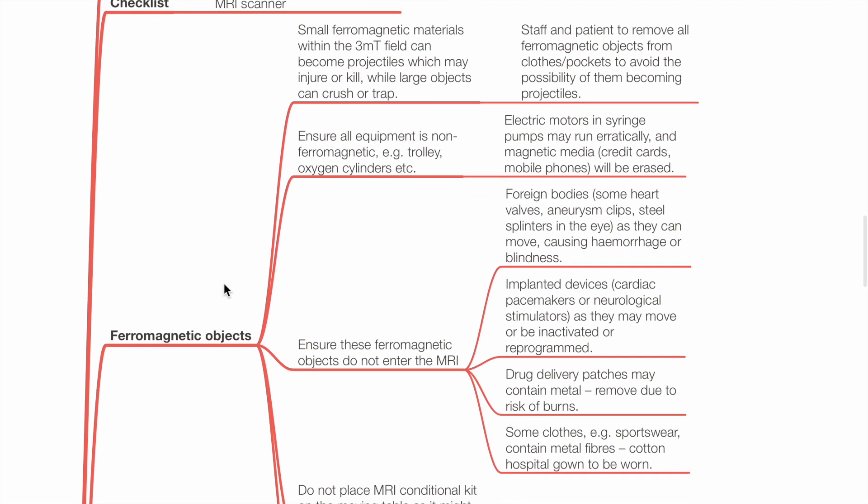Ferromagnetic objects: small ferromagnetic materials within the 3 mT field can become projectiles which may injure or kill. Large objects can crush or trap. All ferromagnetic objects should be removed and placed away from the MRI scanner. Ensure all equipment such as trolleys and oxygen cylinders is non-ferromagnetic.